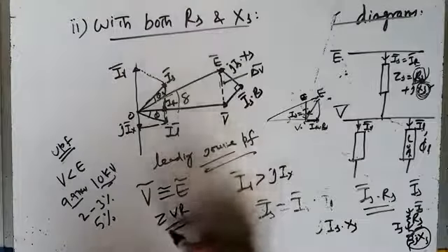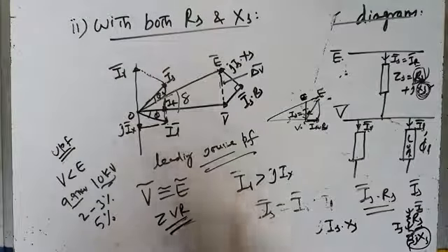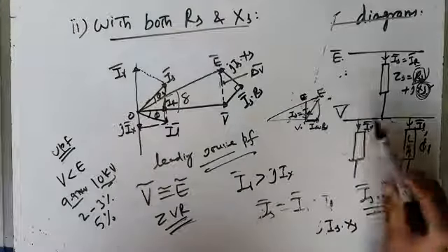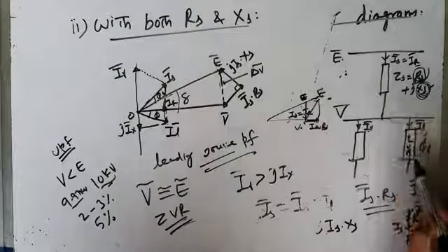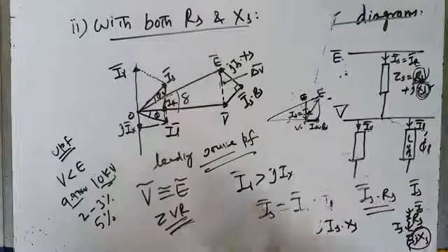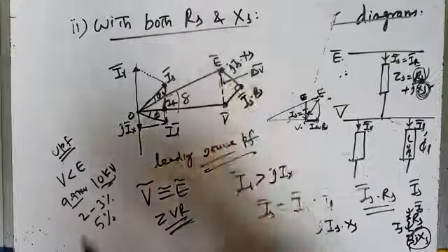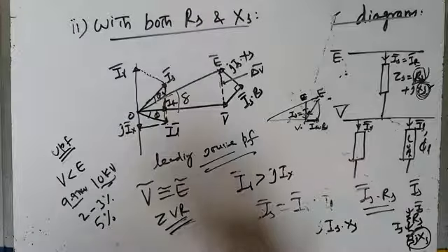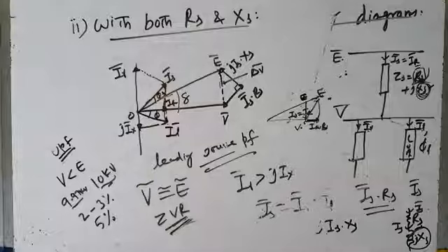On the other hand, if you use this compensator, D-STATCOM, as a voltage regulator in ZVR mode, then this compensator rating will be higher because it has to compensate all the load reactive power, and simultaneously it will inject some reactive power into the source so that the source current becomes leading. It leads the voltage by certain phase angle, and then you will get zero voltage regulation. Okay, so it is better to use it as a power factor corrector for unity power factor operation.